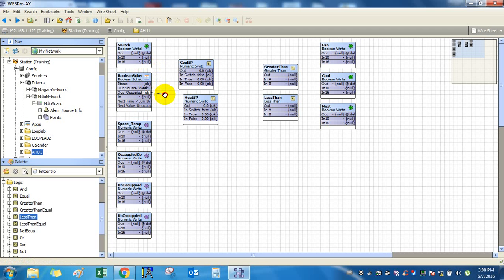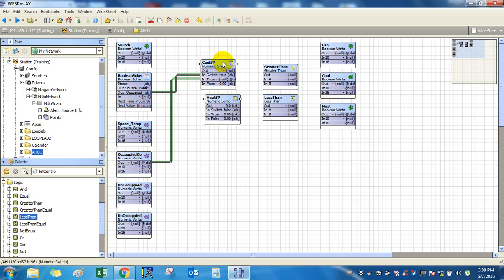So whenever your occupancy mode is there, your schedule will give you 1, and at that time you can pass your occupied cool set point. So here is your occupied cool set point. Link the out pin to input true. And then link the out pin of unoccupied cool to input false. Do the similar thing for the heating set point. Add the out of your schedule to in switch, and then your occupied heat to your input true, and unoccupied heat to your input false.